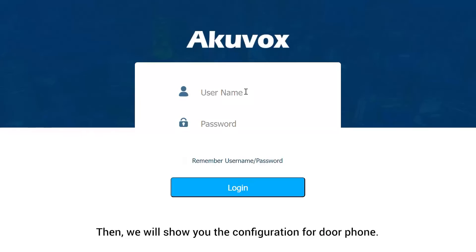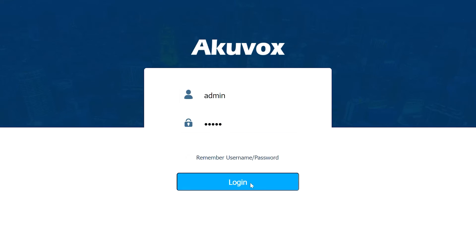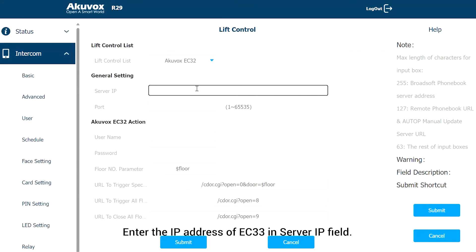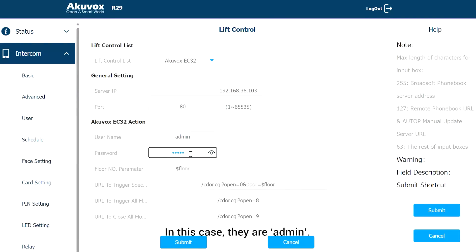Then, we will show you the configuration of the door phone. We will take R29 as an example. Login to the device's web interface with the default admin credentials. Under the Intercom tab, go to Lift Control and select Akuvox EC32 in the Lift Control list. Enter the IP address of EC33 in the Server IP field. Enter 80, which is the default value, in the Port field — the command should be prefilled. Set the username and password to match those of the EC33; in this case, they are admin.